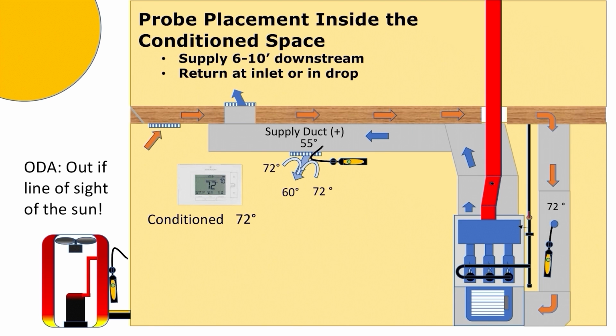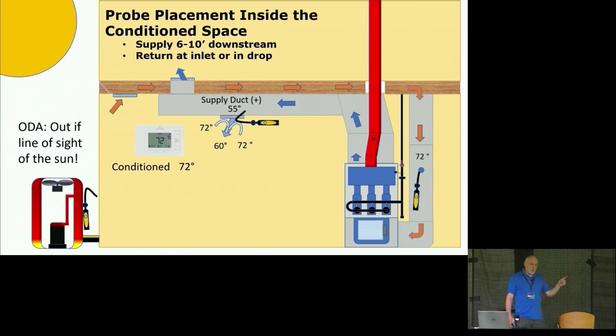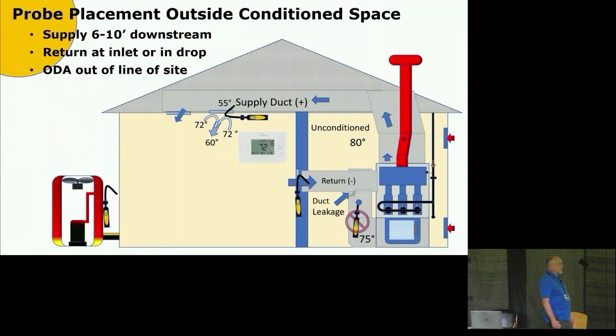The other thing really important to do, make a mental note. Look at the thermostat, see what the temperature is in the space, and look at your return air temperature and make sure that they're the same. If the return air temperature is substantially warmer than your conditioned space temperature, you've got a return duct leakage problem you want to address, right?